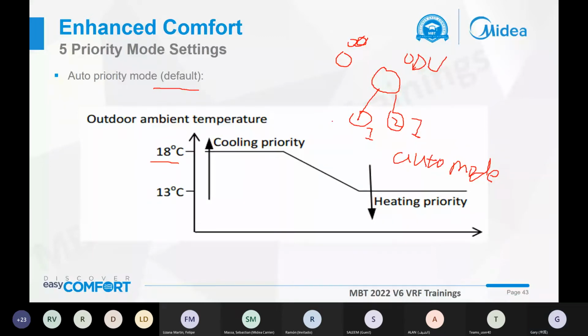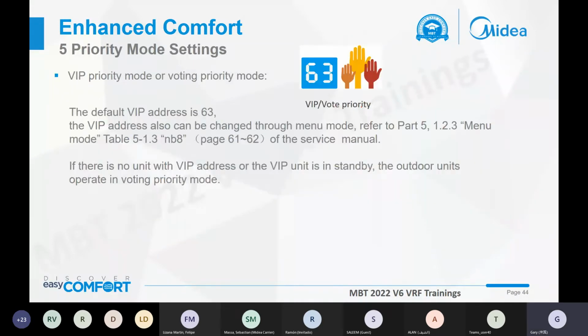If the ambient temperature is less than 13 degrees, the outdoor unit will run the heating mode, and the indoor side will run the heating mode as well. If the temperature is between 13 degrees and 18 degrees, they will have another logic to decide what mode they run. This is the auto mode priority.